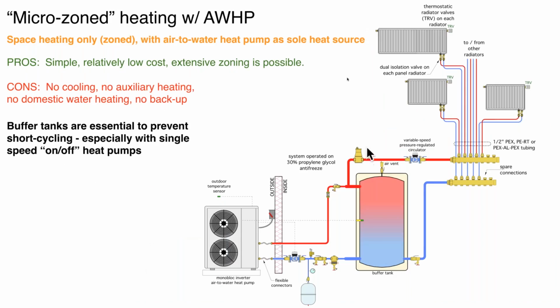So with that, let's start with a residential application. Here's a really simple system. It involves what is called a monoblock air-to-water heat pump. That's a self-contained factory charge unit that would sit outside the building. And you'll see the piping down here that comes into a buffer tank. And in the past, as well as in Hydronics, we've talked about different piping configurations for these buffer tanks. This would be called a 3-pipe buffer tank configuration.